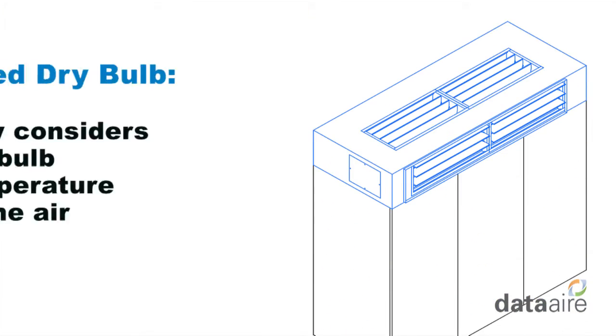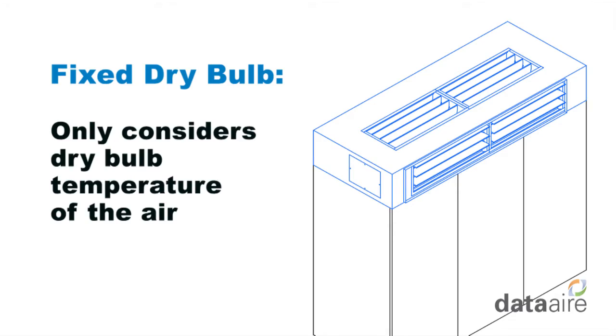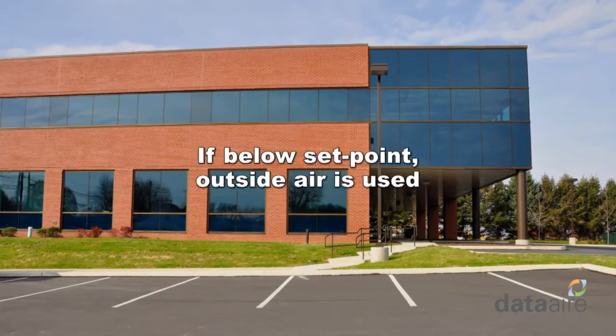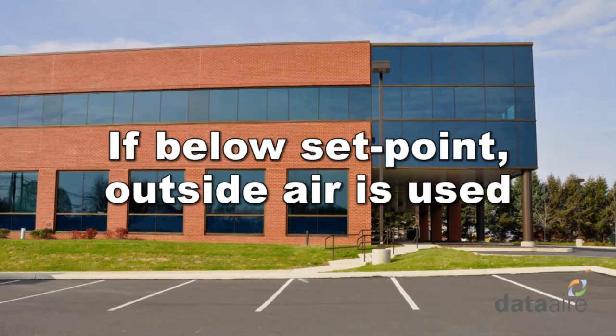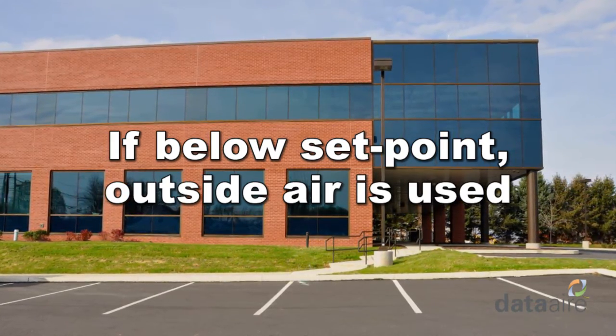Drier air is easier to cool than air with more moisture, resulting in less energy consumption. The fixed dry bulb method only considers the dry bulb temperature of the air. If the outside air dry bulb temperature is below the set point, outside air will be used.